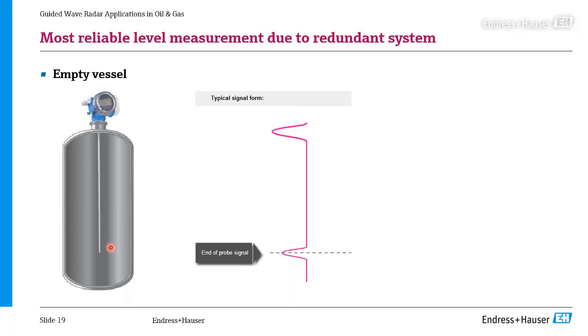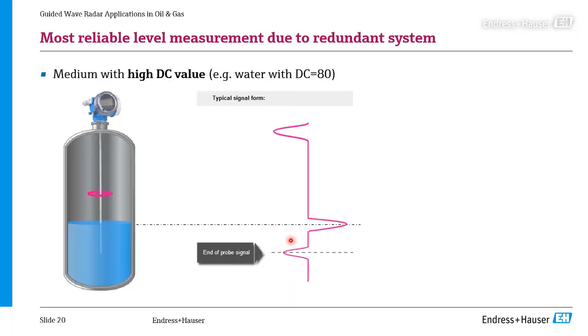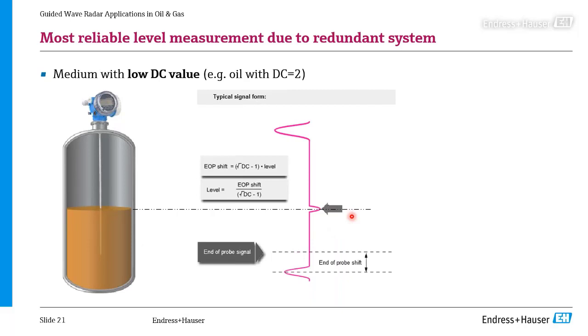So if you look at your screen, you see a junction between the rod and air at the end of the probe. The dielectric constant of the metal probe is sky high, and the dielectric constant of the air or gas phase it's in is very, very low, around 1. So we have a huge jump, and that's what you see on that probe. You get a huge signal back. Now, what happens if you put some level on it? If you put some level on it, and it's, in this case, water, it gets a huge reflection back from the water, because the dielectric of water is around 80. Huge signal. Now, the end of the probe signal you probably won't see anymore because it's water.